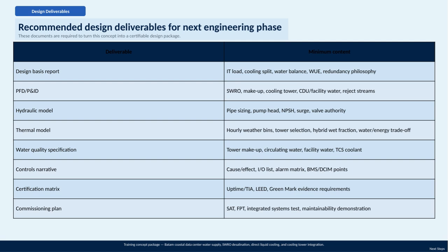Certification matrix documentation will verify that the design complies with uptime requirements like TIA standards, as well as sustainability certifications, such as LEED and Green Mark. Finally, the commissioning plan defines the steps for site acceptance testing, factory performance testing, integrated system tests, and demonstration of maintainability, ensuring the design operates as intended after installation. Together, these deliverables provide a comprehensive framework to move from concept to a fully engineered, certifiable solution.